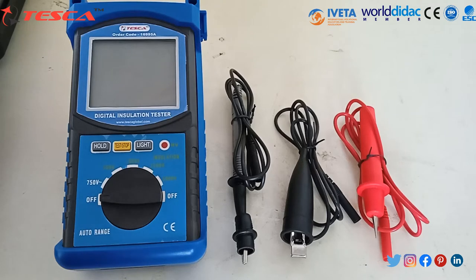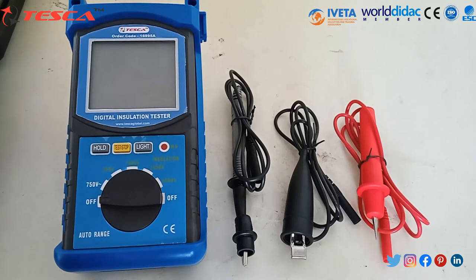This Digital Insulation Resistance Tester series has high performance and safe configuration and improved electro circuit. Output testing voltage can be changed between 100V, 250V, 500V, 1000V, 2500V, and 5000V for different items. The resistance can reach 200 Giga Ohm.